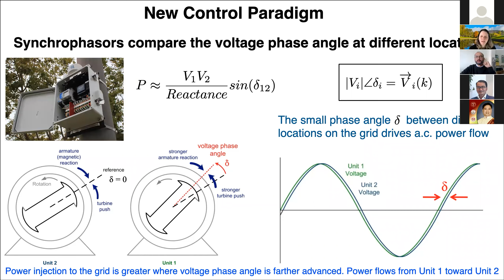The picture here depicts a microsynchrophasor, which is precise enough to measure very small phase angle differences in the distribution grid. This microsynchrophasor is what we commercialized with the team at Berkeley, and it allowed us to rethink how we might control and operate the grid so that we're agnostic to the devices — air conditioner, PV, electric bikes — so that we can just control the grid to facilitate the connection of all of those devices in a way that manages our voltage constraints and thermal limits and allows us to do real-time control.